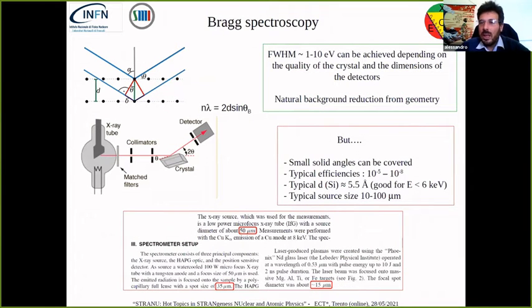So if one wants to get rid of the standard solid state detector, one of the natural candidates is Bragg spectroscopy that you know very well probably, which tells you that if you have some X-rays or photons in the X-ray range which are impinging on a crystal, they are reflected following this rule here. I don't know if you see the mouse. And in this way, if you put a position detector at the end of the line, you can really see a nice energy spectrum. Full width of 1 to 10 electron volts can be achieved with this kind of technique, depending on the quality of the crystals and on the dimension of the detector. And also a very nice feature, a sort of natural background reduction, which comes from the geometry, because you see that the detector is usually put not in direct line to the beam.